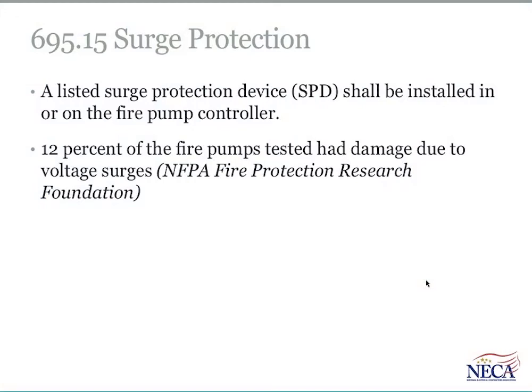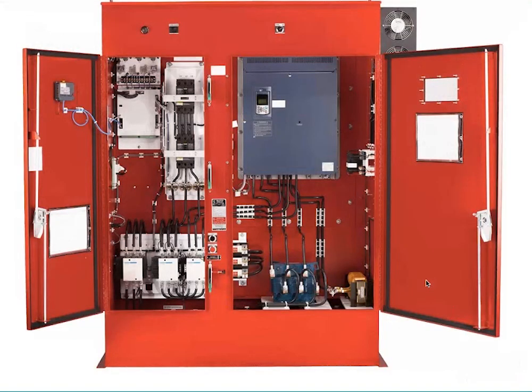Article 695 provides rules for fire pumps, and we see a change here to require a listed surge protective device be installed on the fire pump controller. The substantiation pointed out that roughly 12% of the fire pumps tested after they were initially installed had damage due to voltage surges. So last code cycle, we saw a new requirement put in place for switchboards and panelboards used on emergency systems to have surge protection as well. A lot of this type of equipment has sensitive electronics in it and can be vulnerable to surge events that can cause damage. So a requirement is now in place for surge protection on fire pump controllers.